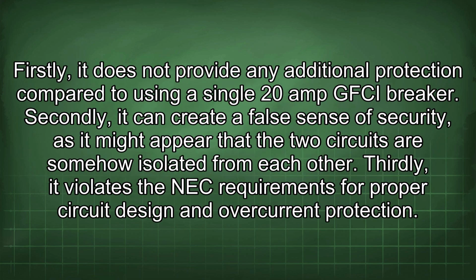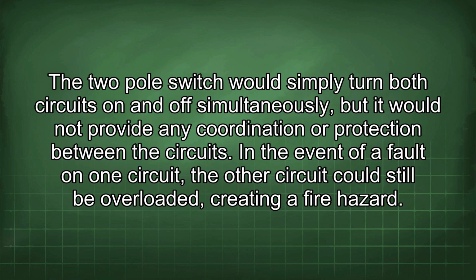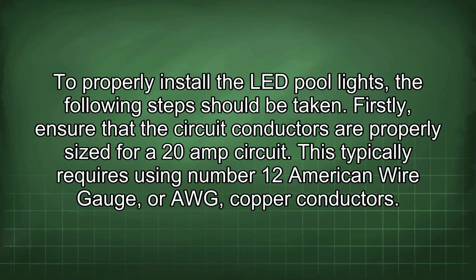Firstly, it does not provide any additional protection compared to using a single 20 amp GFCI breaker. Secondly, it can create a false sense of security, as it might appear that the two circuits are somehow isolated from each other. Thirdly, it violates the NEC requirements for proper circuit design and overcurrent protection. The 2-pole switch would simply turn both circuits on and off simultaneously, but it would not provide any coordination or protection between the circuits. In the event of a fault on one circuit, the other circuit could still be overloaded, creating a fire hazard. To properly install the LED pool lights, the following steps should be taken.